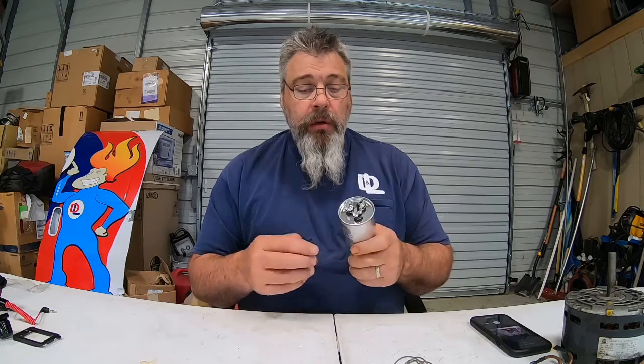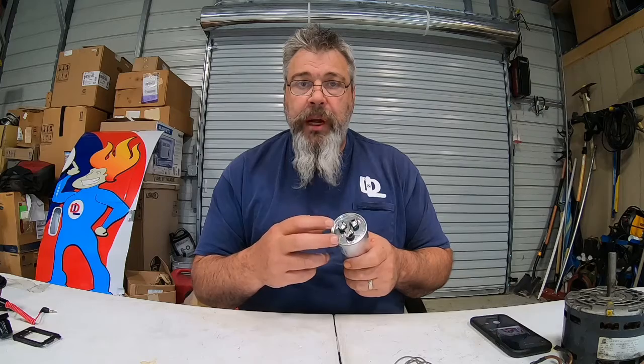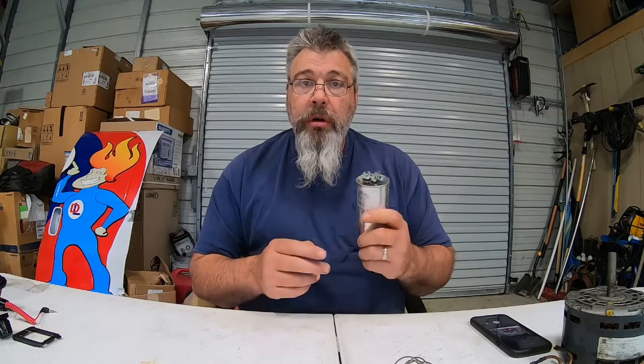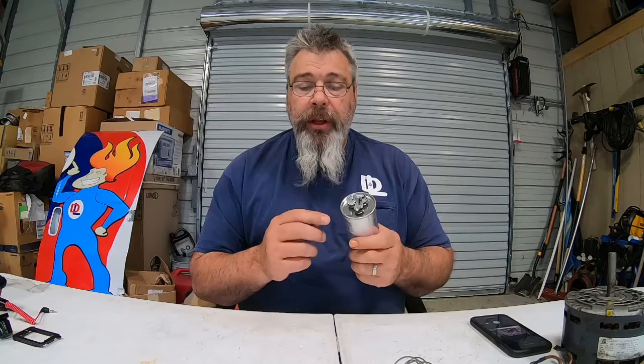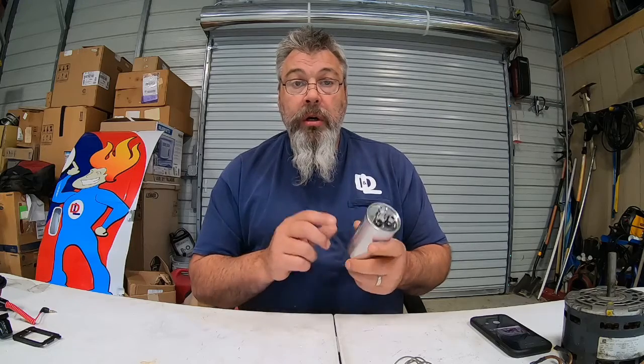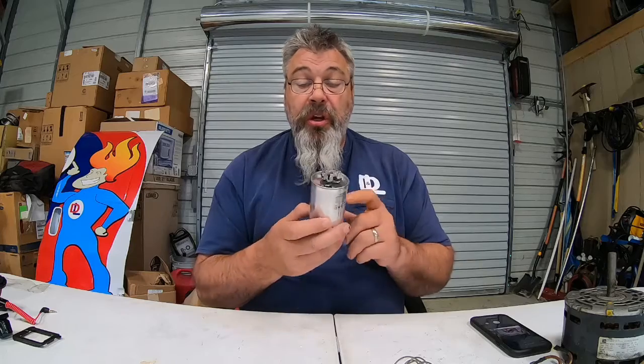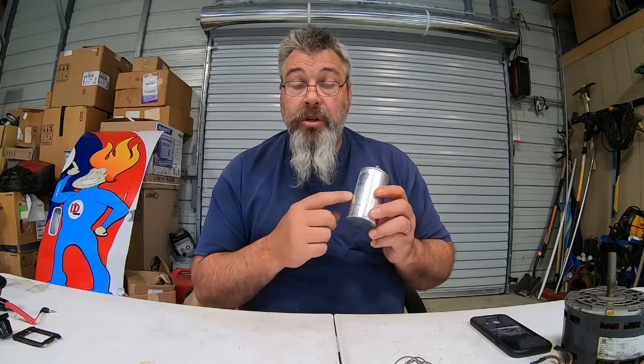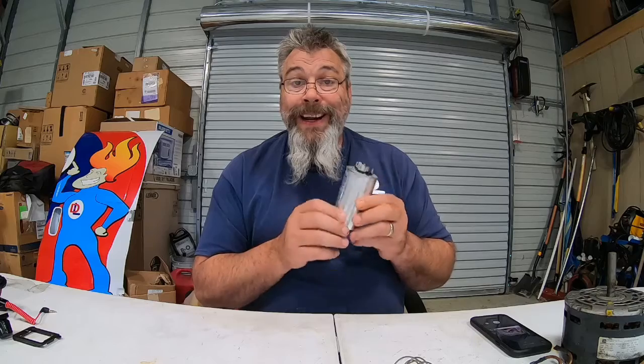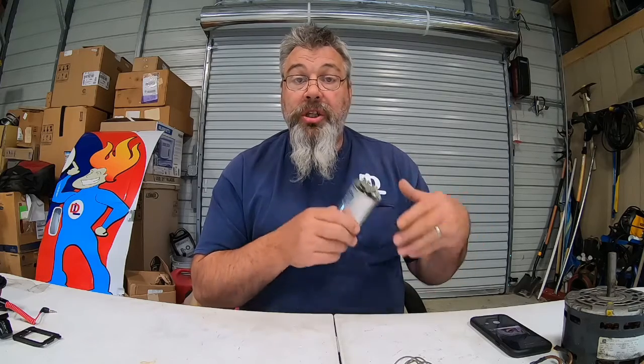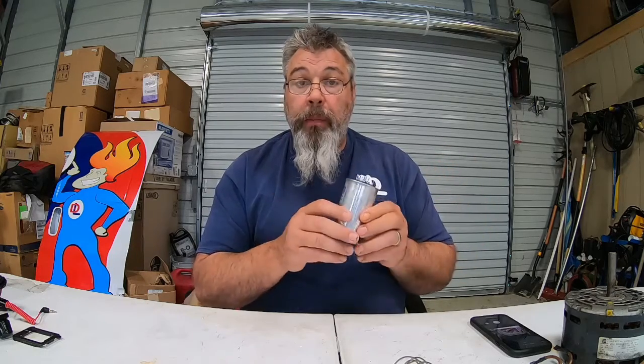These can be checked. We have to check these with ohms of resistance, and microfarads is how they test them, and we make sure that these are up to par. For instance, this one is a 50-5, which means it uses 50 microfarads for the compressor and 5 microfarads for the fan motor. How we test these is to make sure that they meet those requirements. So this is all stuff that we test during our preventive maintenance. A capacitor actually stores energy inside of it to help your outdoor unit start up and run. Okay, so that's one component that we have.